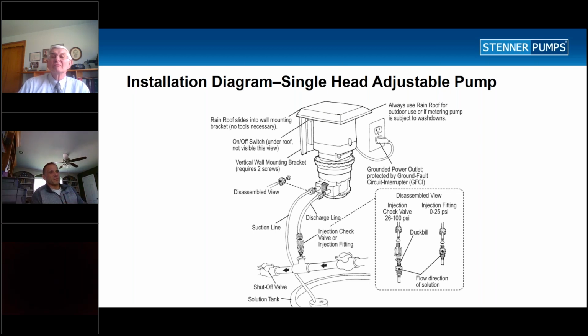So when we send the pumps out, we have 2 injection fittings. Every time that you order a pump that's rated for 25 to 100 psi, you're always going to get a check valve with a duckbill. So every time that you're changing tubes, we recommend also replacing that duckbill. What the duckbill does is it guards against back pressure, backflow. So in a lot of cases, if we see splitting tubes on the pump, more than likely a split tube is caused by a worn duckbill. So it's always a good thing just to change the duckbills every time you're changing the tubes.